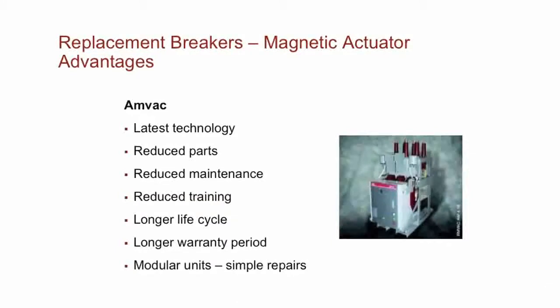When we look at replacement breakers, I use the medium voltage primarily in this presentation. I mentioned the low voltage, but I'll focus on medium. If you haven't seen it, I welcome you to come down to the show floor and take a look. We've got magnetic actuated breakers across almost all our product lines now, from the outdoor distribution breaker to the reclosers to our rolling replacements to our standard indoor switchgear. We use that same element on all the medium voltage breakers. What you see here is a GE Magnablast breaker, I believe, and we basically just bolt all the parts on it so that it adapts and fits into the existing GE cell.